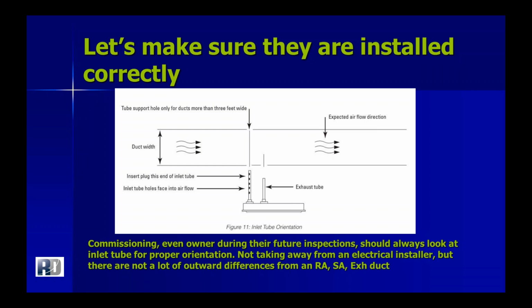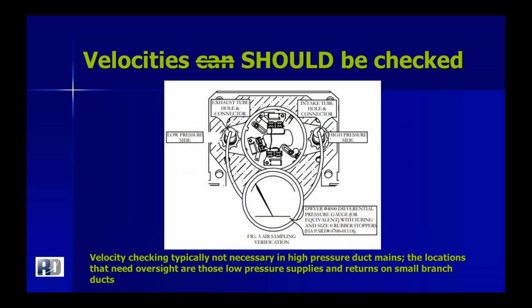And how would an electrician, not necessarily poking around, even know the direction of air in a vertical shaft, because maybe he doesn't even know where the air handling unit is located? Is the air handling unit in the basement, or is it up in the penthouse? So which direction does the airflow go? We'll stop there. But the orientation of that duct detector sensing tube is very important. We're always peeking our head into the access doors to make sure they're the right direction. We also advocate during training that the owner, when they're doing their inspections and are already in there looking, should make sure the sensing tubes are pointed in the correct direction.